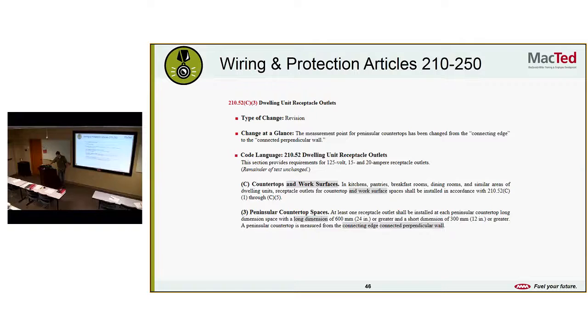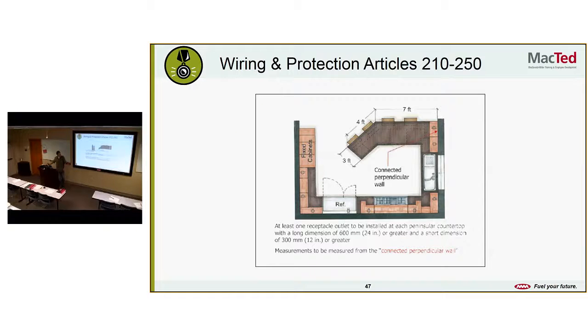Okay. Dwelling unit receptacle outlets. Revision. The measurement point for peninsular countertops has been changed from the connecting edge to the connecting perpendicular wall. I think this is what they're talking about. They're clarifying that you can have an outlet over here against the wall, and that will serve this peninsula. Because where else would you put an outlet? You'd have to drill it in and have it surface mounted into the countertop, because there's no wall there.